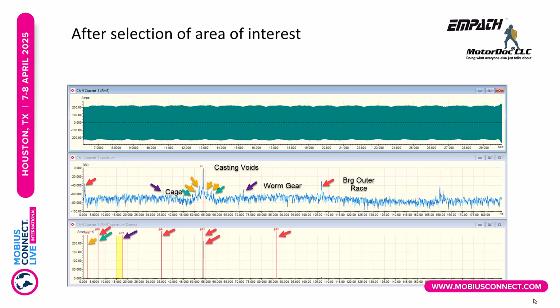So they have pole pass frequency sidebands, cast aluminum, meaning casting voids. You don't really condemn a machine for that. Plus then we also have some cage peaks. We have something related to the worm gear, and then we have an outer race peak. The very bottom is something called demod, where we take the line frequency out. That's great, but I can't really use that for troubleshooting other than to identify peaks exist. The reason for that is because I have nothing to compare it to, because I have to go from the top down, not the bottom up.